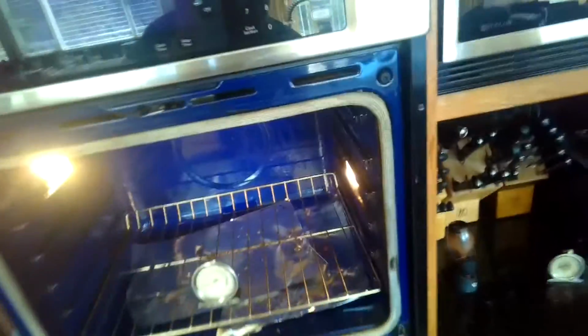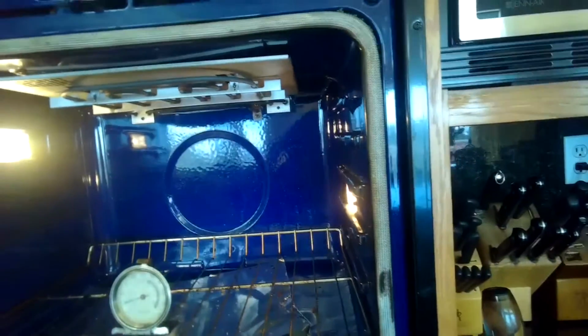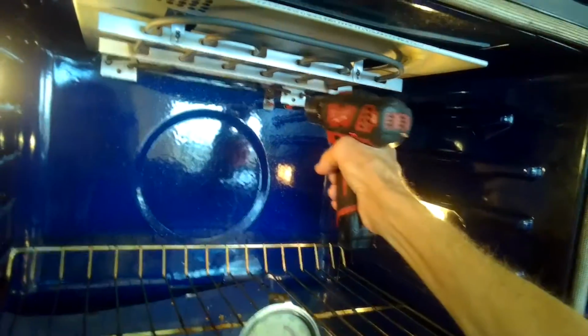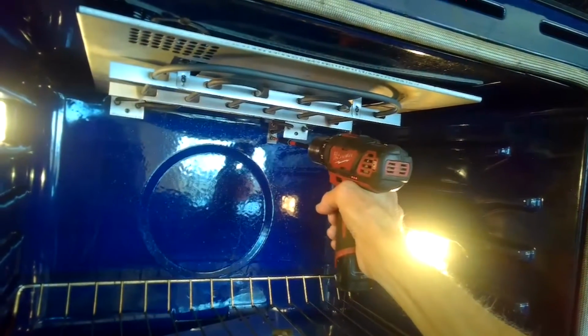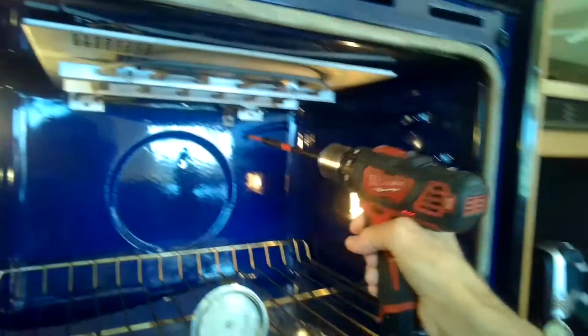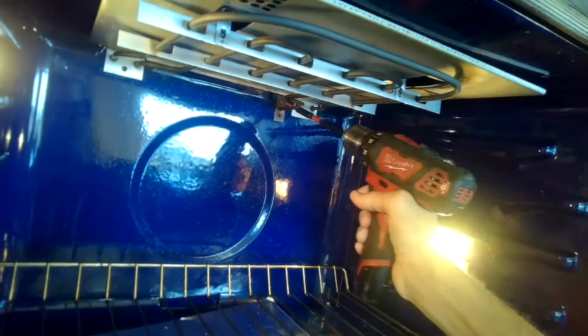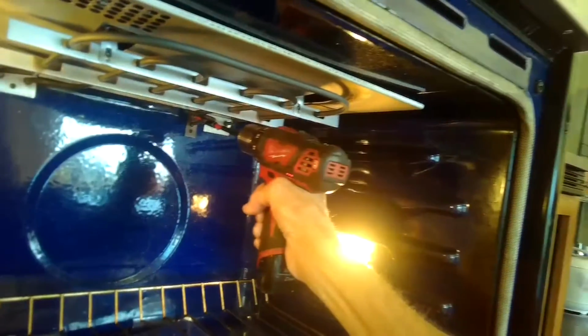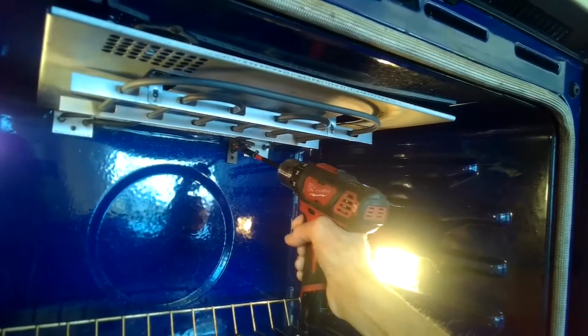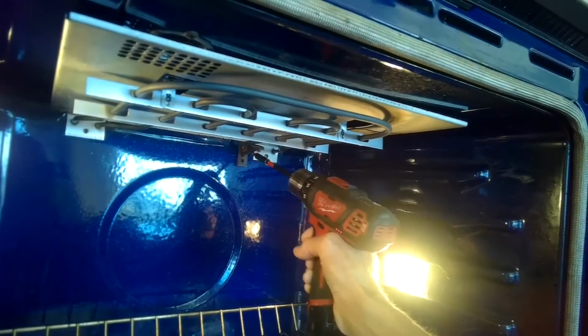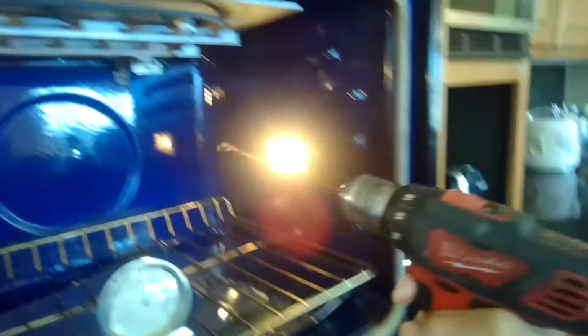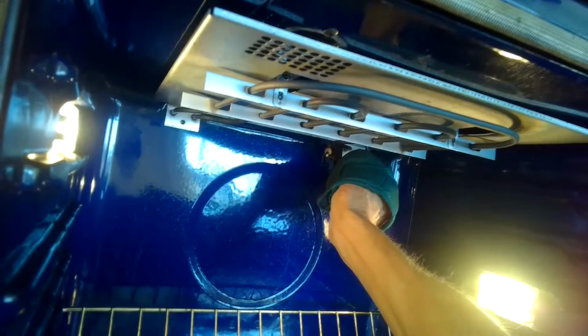And now it's still hot in there, so I'm going to pull out this rack using a mitt, and then I'm going to be removing and replacing the oven temperature sensor. It could be that the sensor is defective, so it's pretty easy to do. I'm going to remove a couple of Phillips head screws. It's still a little bit hot in there. It's best to let it cool down. And there's one at the bottom, one at the top, so get those out, and then I can pull the temperature sensor toward me, and then I can pull gently on the wire, and there'll be a connector connecting the sensor to a wire that I just have to squeeze in on a tab and pull the two pieces apart.